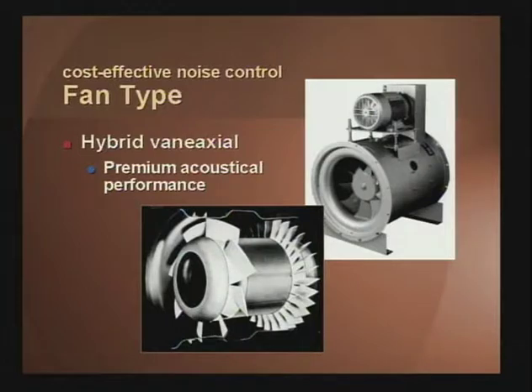The last fan type available in these products is your hybrid vane axials. These are your premium acoustical performance fans. Typically, they have very tight tip clearances and are designed to treat the air in a straight through forward fashion. They're characterized by extremely low inlet sound levels as well as discharge sound levels. These products are available today in both horizontal and vertical configurations, which is something fairly new. In the vertical configuration, you get the advantage of the vane axial type fan, but you also get a footprint for the unit that's about the size of a plenum fan.